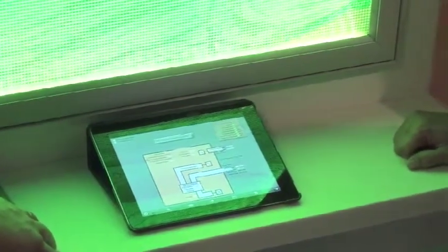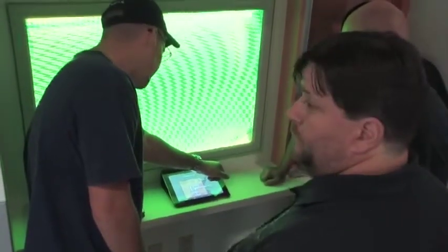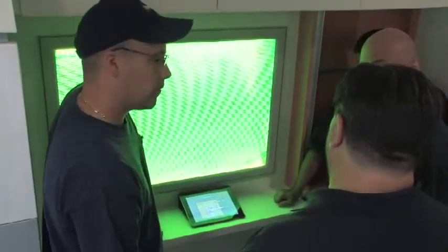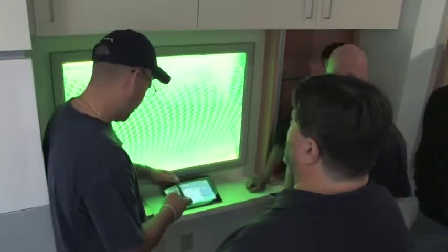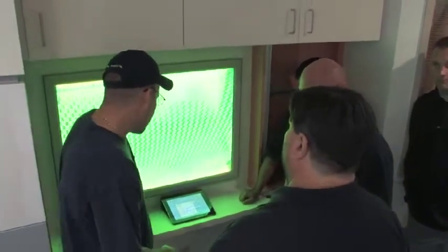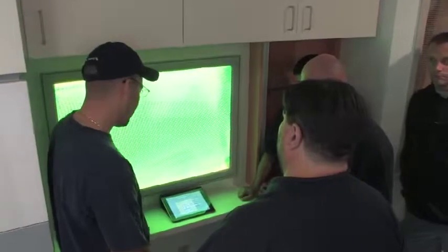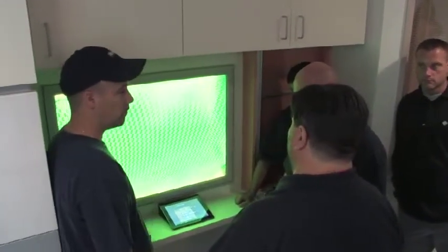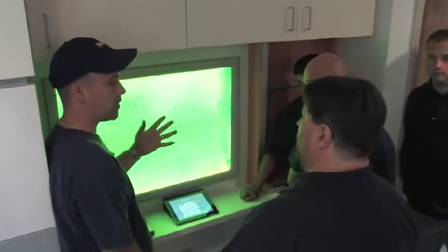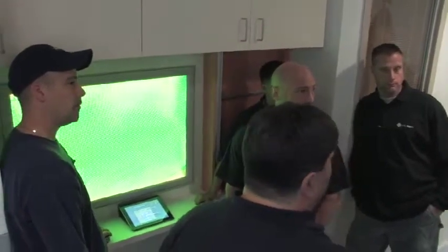Will that bring in an alarm if you had that hooked up? Yes, because you have your humidity high and low settings. These fan power boxes, do they have a 3-position switch, or is it set at 1 speed? The fans are set for 1 speed, per what the balancer set them up for. So they're not going to change once we turn them on, whatever they're set at. I think they're back pressure modulating though, right? Bonnie, can you help me on that? Don't they have a fan that adjusts for the filter loading?